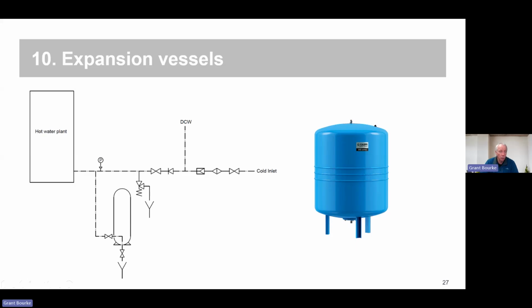Isolate this from the plumbing system. Open this to air, and then pump this up to the pressure that you've basically observed in the system. If it's a bigger one on a bigger building, if you've had a lippy apprentice, you can give them a bike pump and a 300-litre tank, and that'll shut them up for a while.